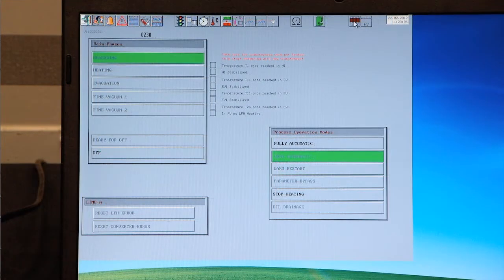If the LFH is being run in a mobile environment, then the semi-automatic mode should be selected, and the process will stay in each stage, measuring, heating, and fine vacuum, and the operator has to manually transit the process to the next stage.